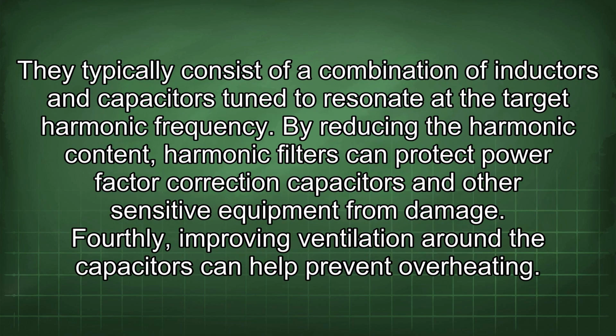They typically consist of a combination of inductors and capacitors tuned to resonate at the target harmonic frequency. By reducing the harmonic content, harmonic filters can protect power factor correction capacitors and other sensitive equipment from damage.